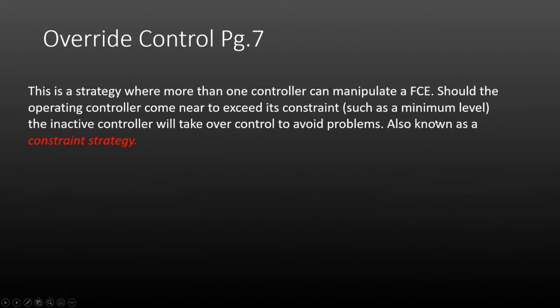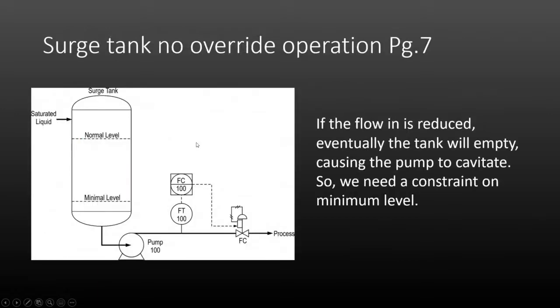Override control is another safety-oriented strategy where more than one controller manipulates the final control element. Should the operating controller come near to exceeding its constraint — which can be any type of limit or situation we don't want to encounter, such as a minimum level — the inactive controller will take over to avoid problems. We call override strategies sometimes constraint strategies.